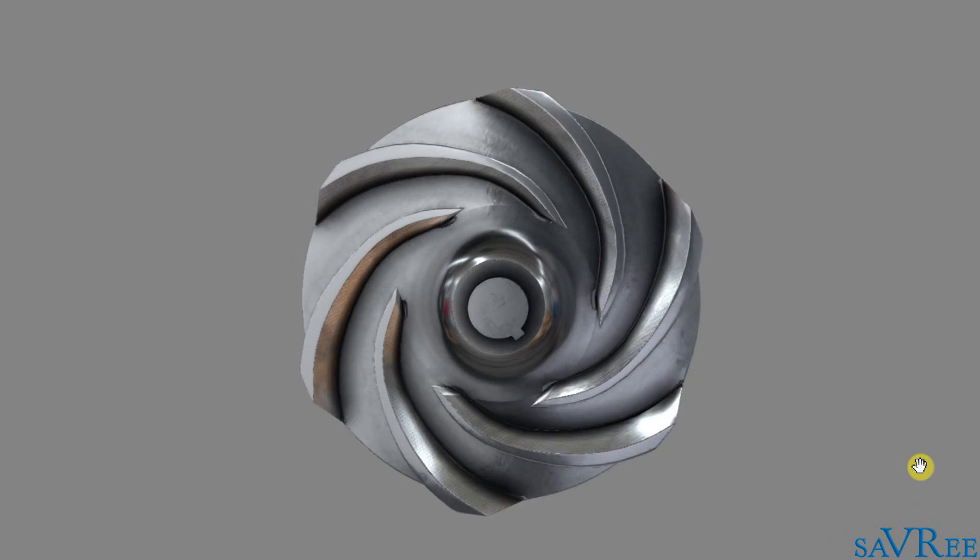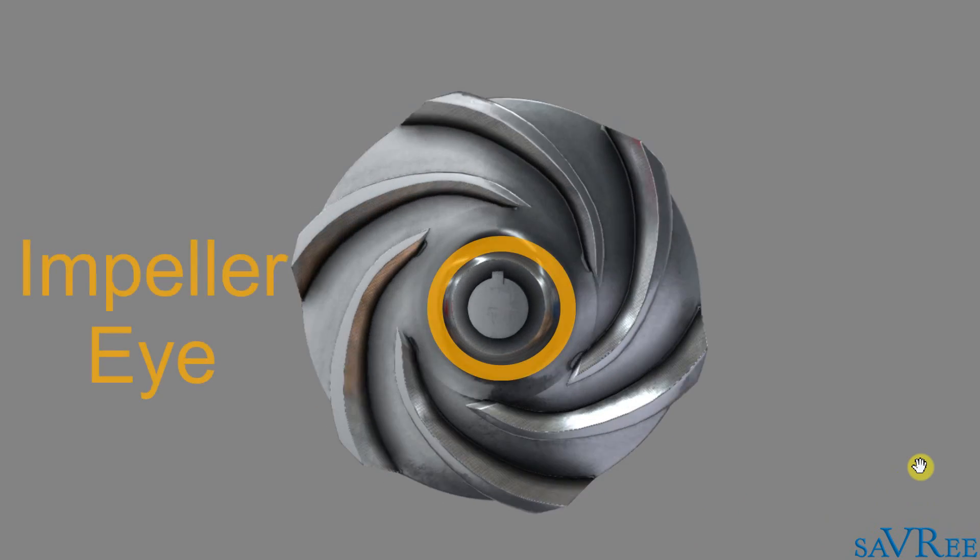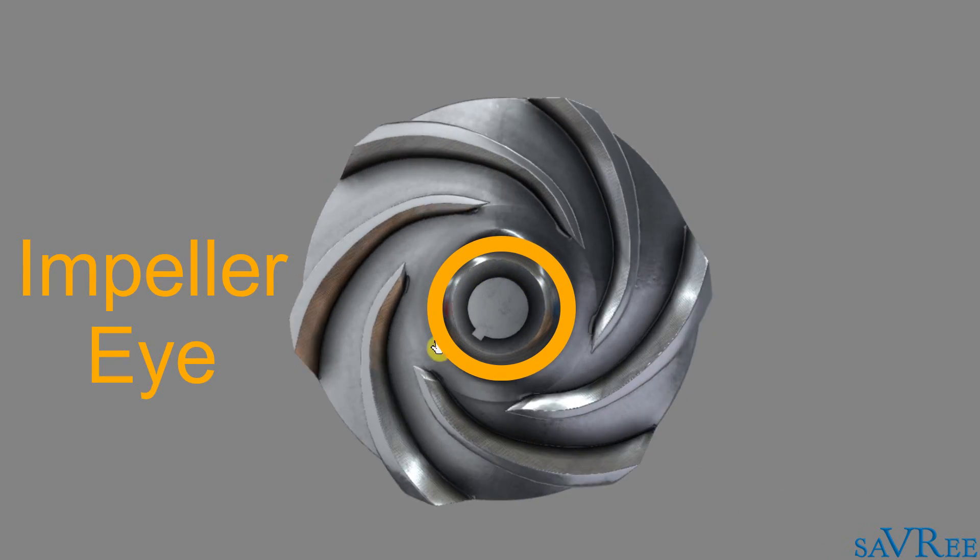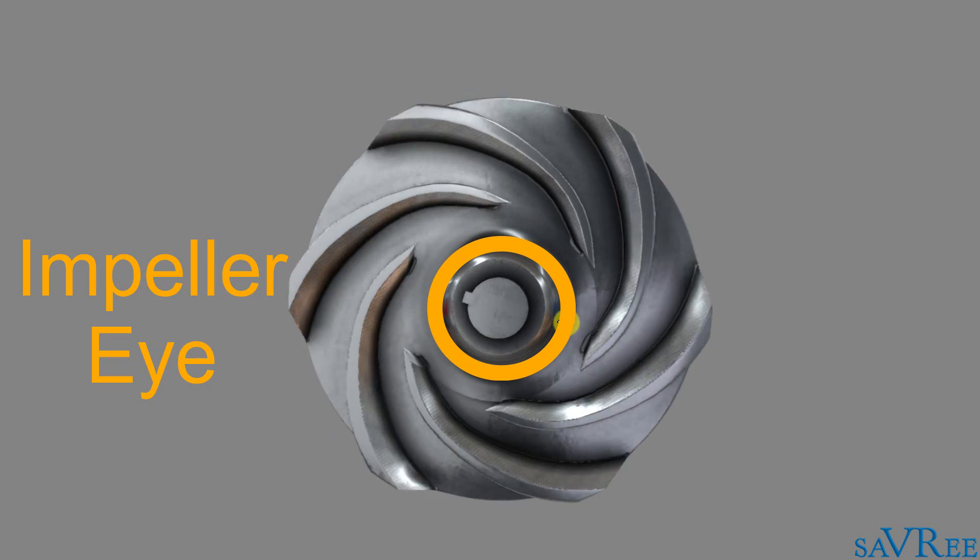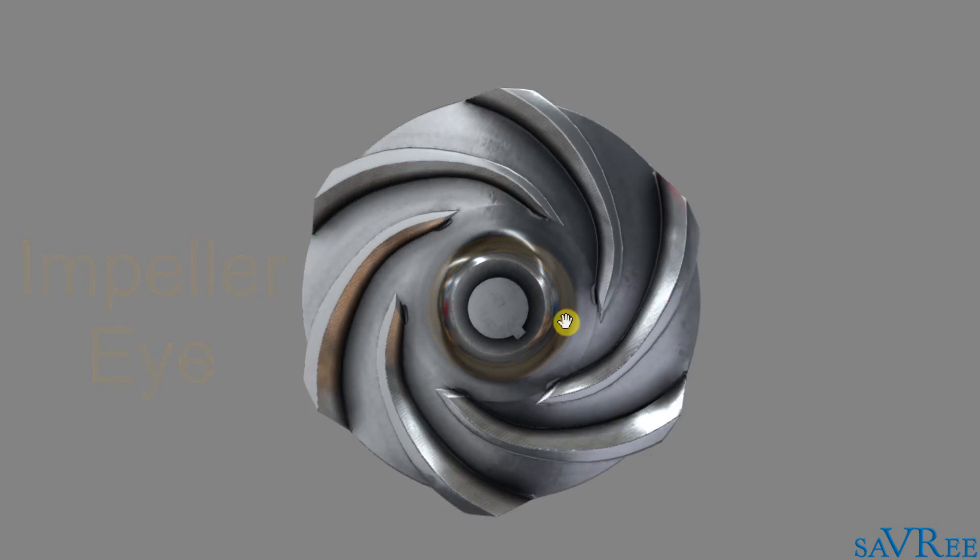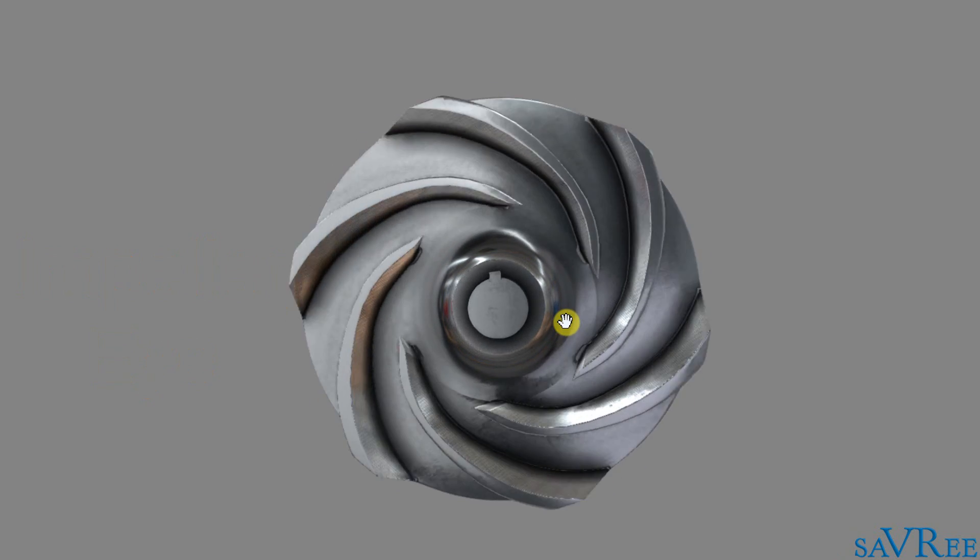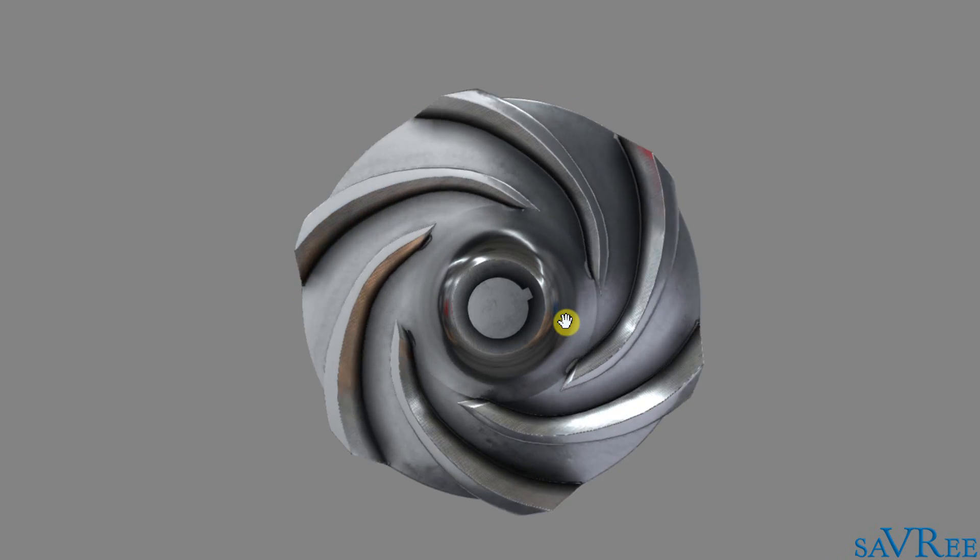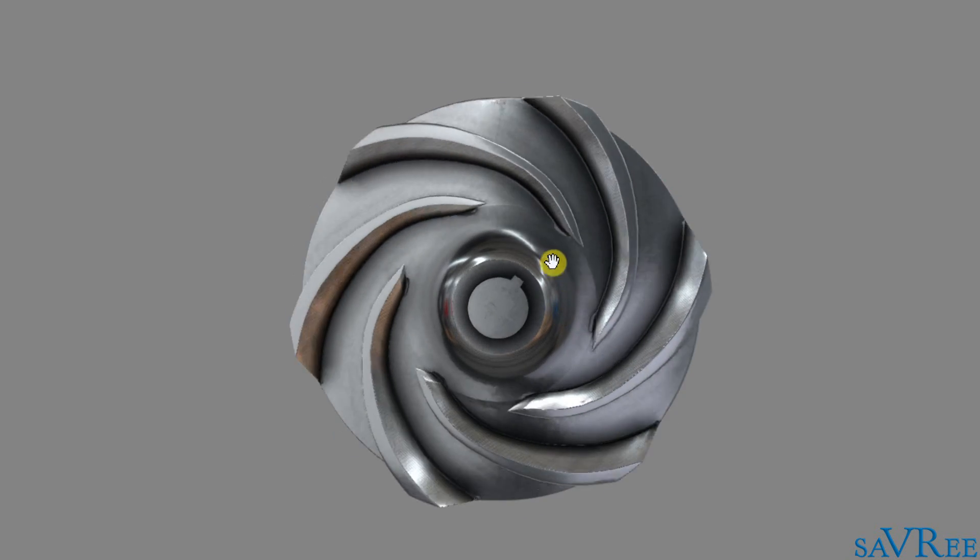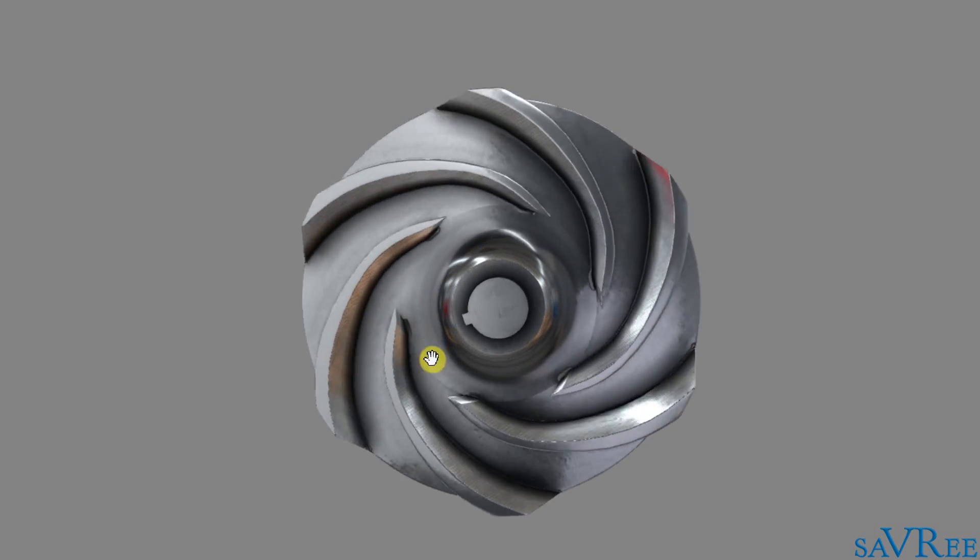The suction side of the impeller is this middle area here. That's what we call the eye of the impeller. And as we draw the liquid in, we're going to create a negative pressure at the eye of the impeller. And then we're going to throw the liquid outwards radially, away from the center of the impeller, towards the outer periphery of the impeller.